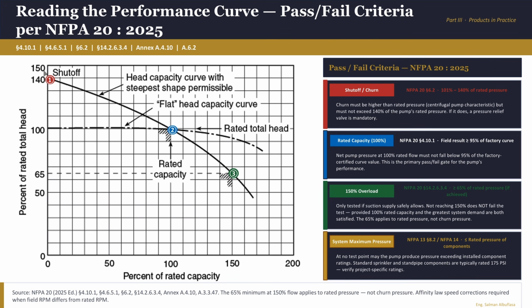Shut-off is number 1, right here on the chart. The pump is running but nothing is open. No sprinklers, no flow. That's the highest pressure the pump will ever produce. And it must stay controlled. Too high and you're still blowing out your entire system. As we can see here, churn must be higher than rated pressure, but must not exceed 140% of the pump rated pressure. If it does, a pressure relief valve is mandatory. That's criteria 1.